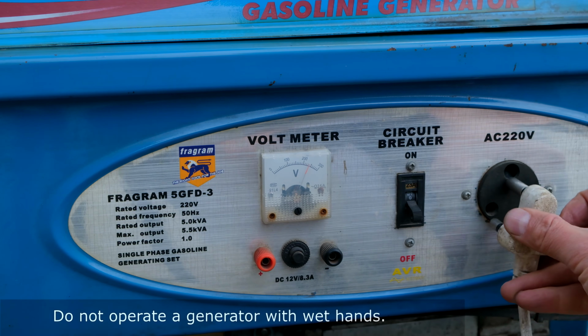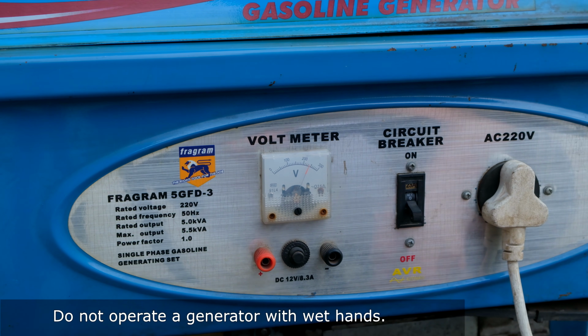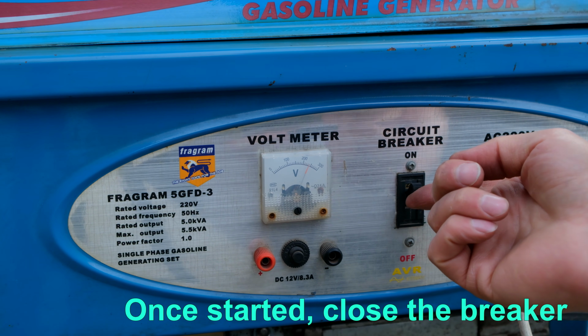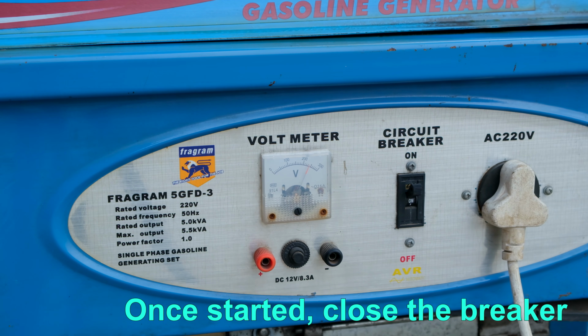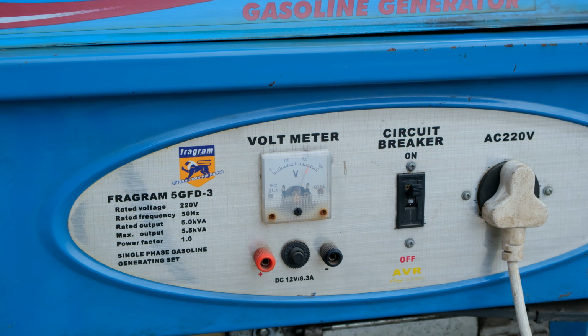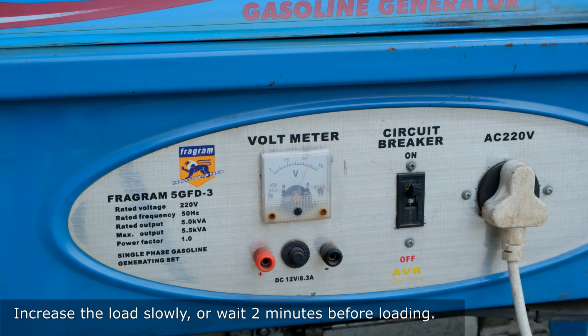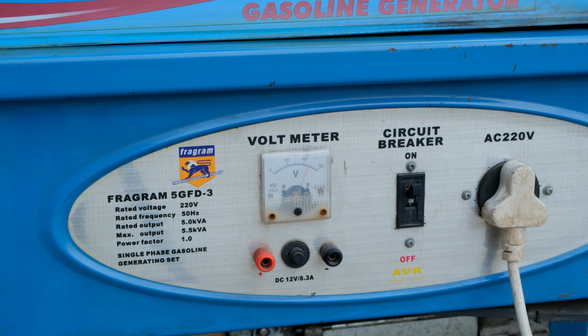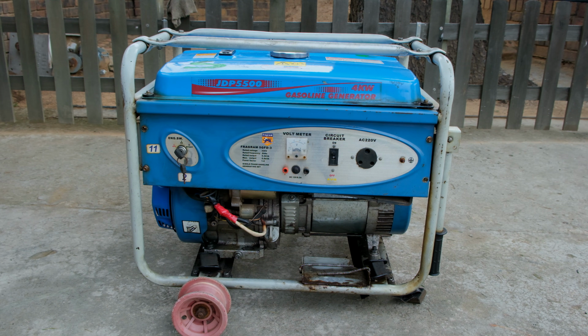I can now plug in my first appliance. Close the circuit breaker. Remember that the generator must not be put at its maximum load shortly after being started. Allow it to have enough time to warm up. If you do need to run the generator at a high load, make sure you never exceed 75% of the max rated wattage. If you're going to be unplugging your load, best to switch off the generator shortly afterwards.